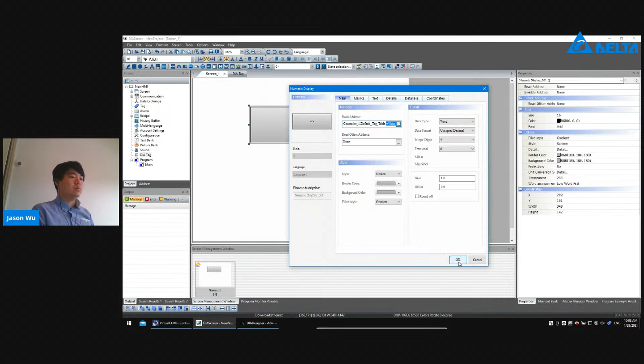The DI tag also has a certain format. It will start with DI_tag, then the controller name in DIADesigner, then a dot, the table name in the global variable, and in the end a dot and the variable name. Click OK, and that's the DI tag part. It's really easy, when you design the HMI screen, you don't need to remember the address from a PLC, you can just use this variable directly.